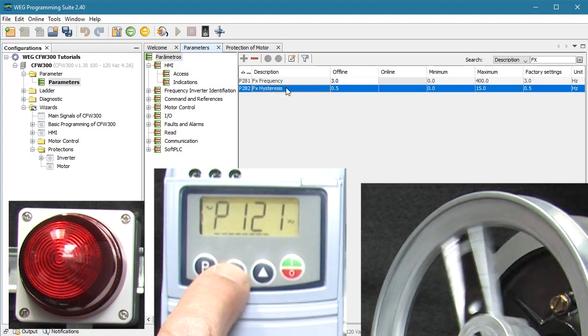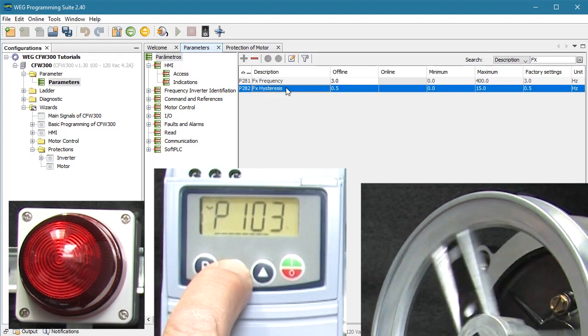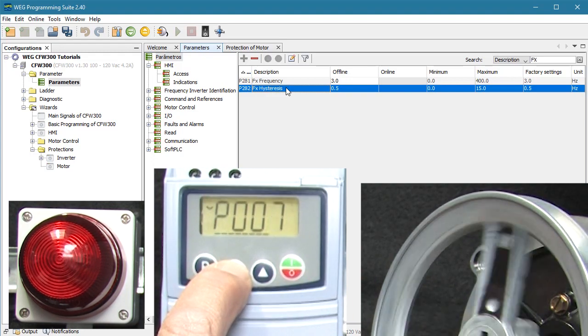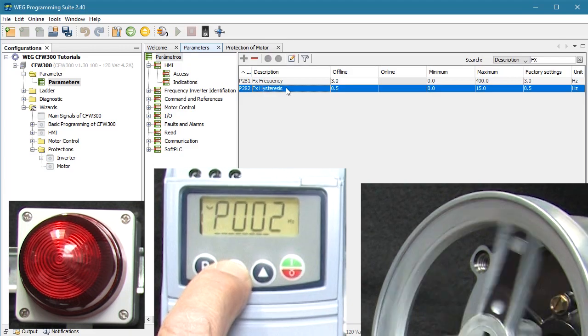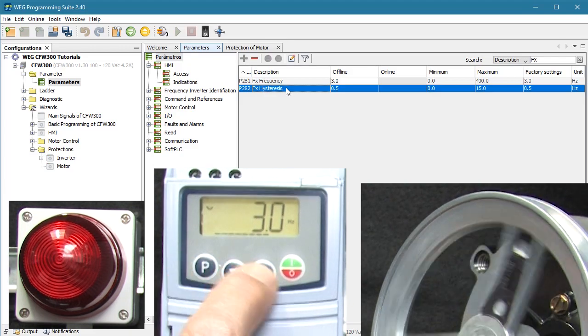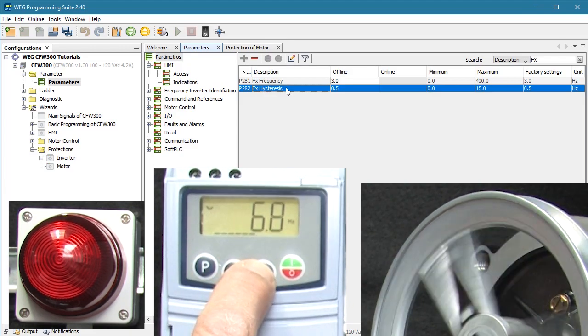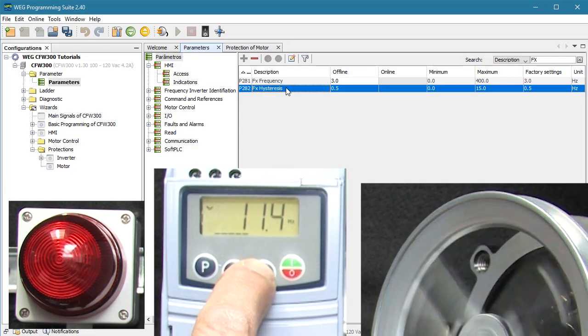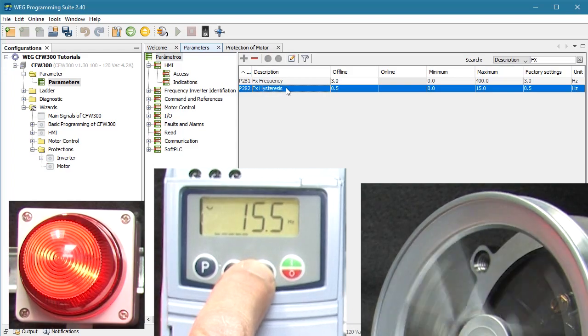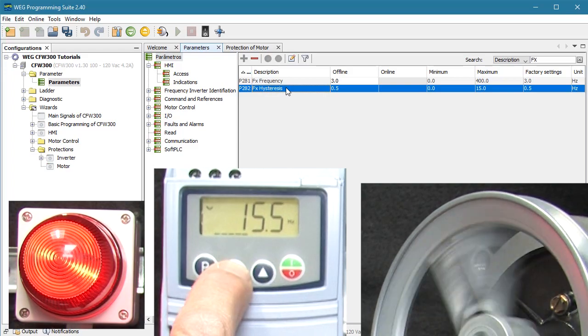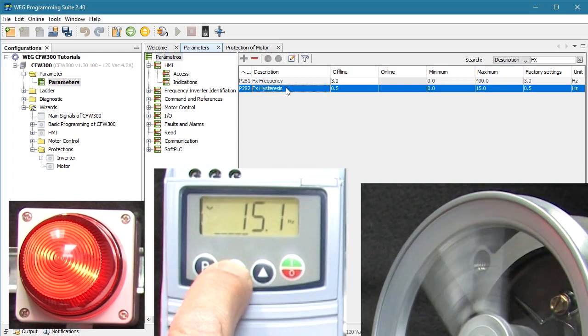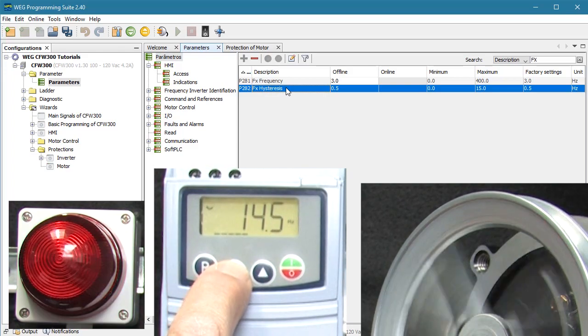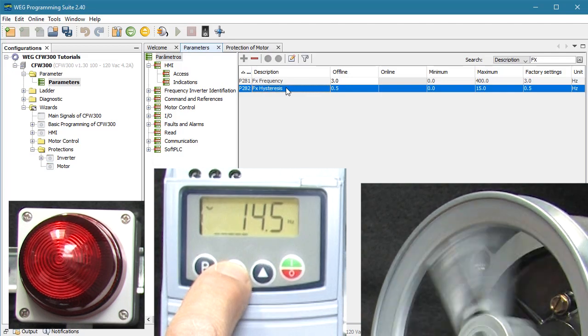Let's try it. If I hit run and scroll down to the frequency display parameter, we see that the drive is running at the 3 Hz we entered. I'll scroll to 15.5 Hz and sure enough the light turns on. Now I'll scroll down to 14.5 Hz and the light turns off.